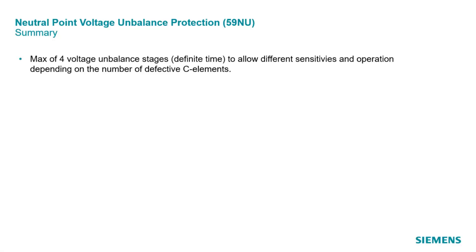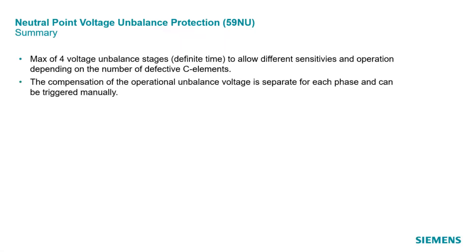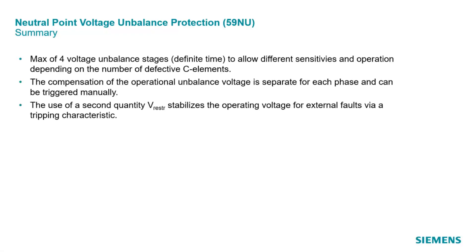A maximum of four definite time voltage unbalanced stages are implemented to allow different sensitivities and reactions depending on the number of defective capacitive elements. The compensation of the operational unbalanced voltage is separate for each phase and can be triggered manually. The use of a second quantity V-restrained stabilizes the operating voltage for external faults via a tripping characteristic. For the detection of very small operational voltages, SIPROTEC 5 provides a very high sensitivity of 0.1 percent of the nominal voltage of the capacitor bank.